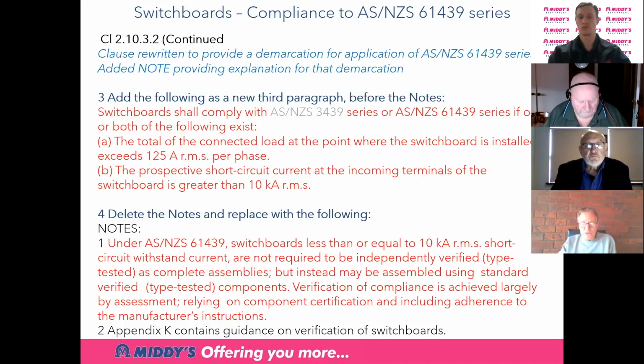Appendix K contains guidance on verification of switchboard. Appendix K hasn't been modified or amended. All the information is in there. Appendix K 2.3 covers testing, and K3 is application. We've had a lot of correspondence from switchboard builders about this. One of the members of the committee has spent a lot of time working with switchboard builders as to verification of switchboards, and the fact that 3439 and 61439 currently are both okay. If the switchboard is tested to 3439, it will be okay as per 61439. Next slide, please. And that's Roy.